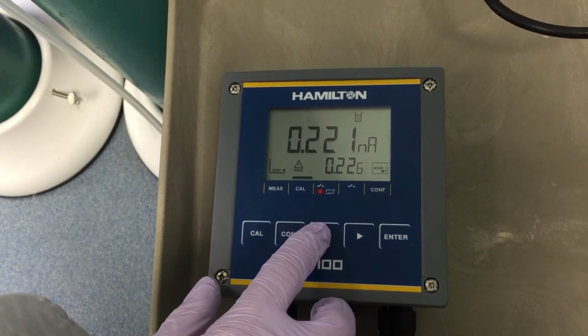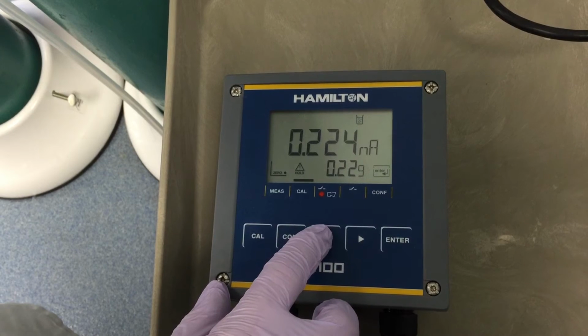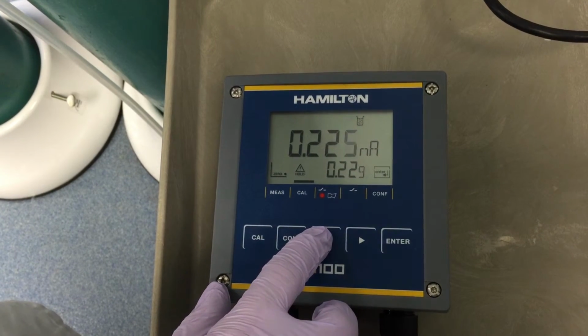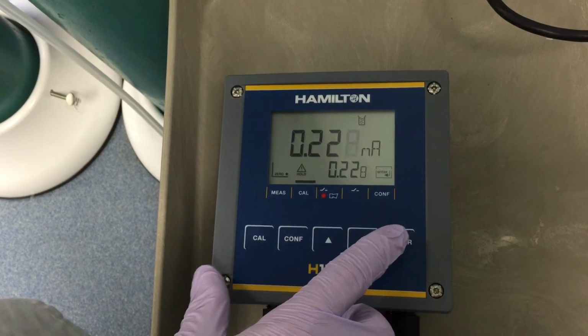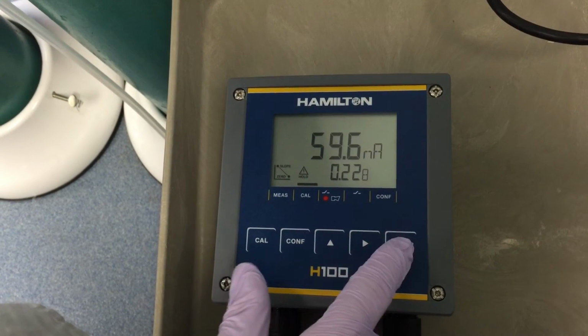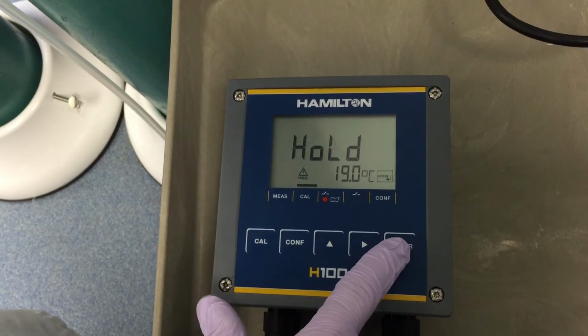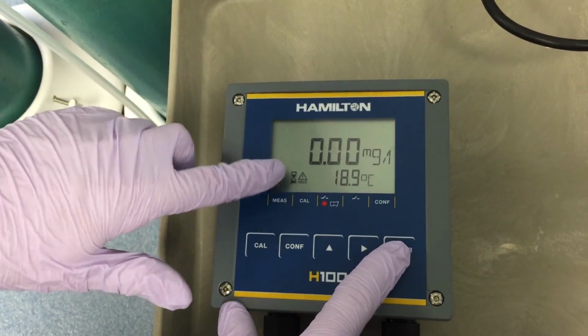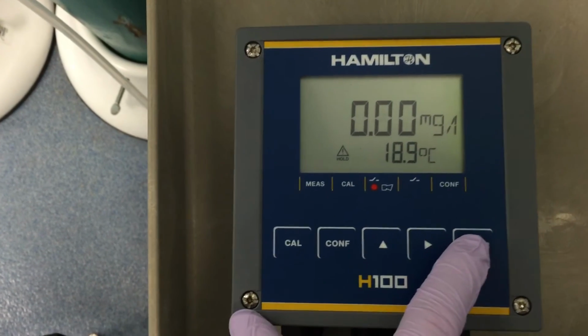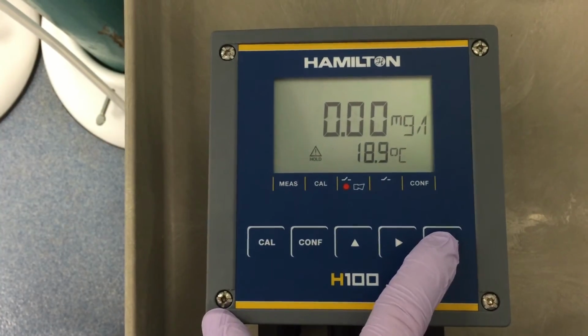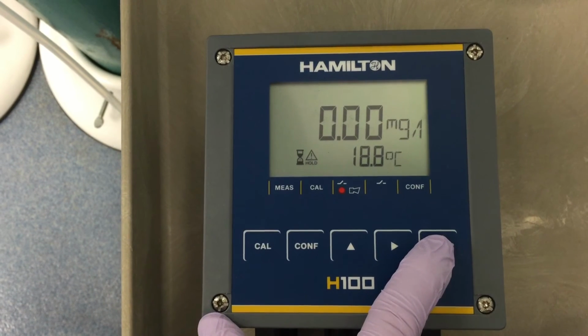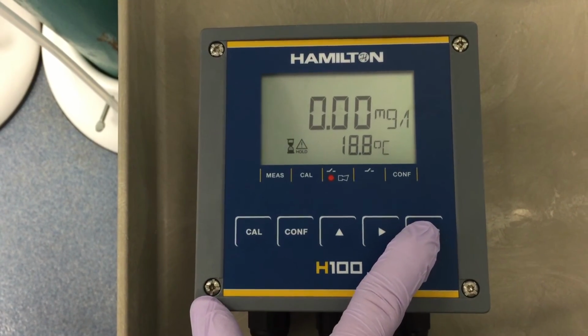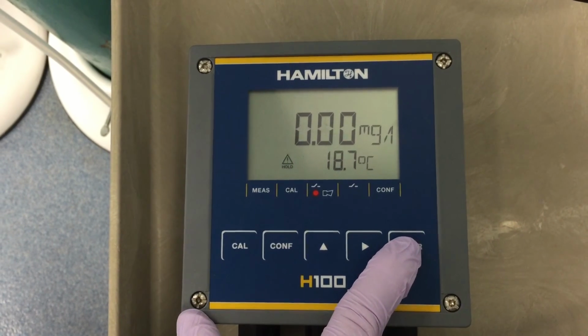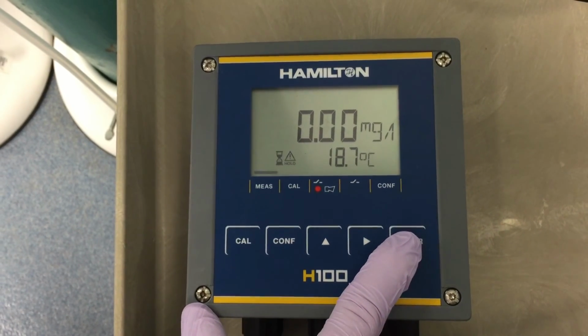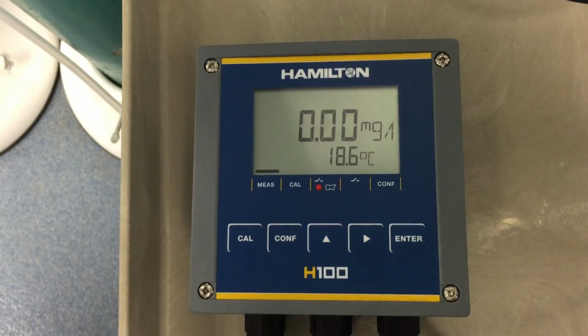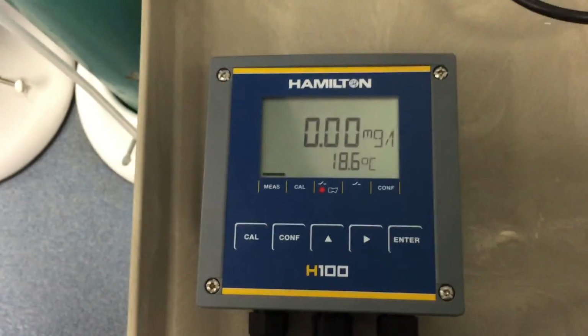I'm going to go with just what I had it at before. Kind of bouncing around that range. Okay, then you hit enter. Enter, and you hold that down. This will blink for 30 seconds, and then you hold this button down until that's finished blinking, and then your zero calibration will be finished. Okay, that's the zero calibration.